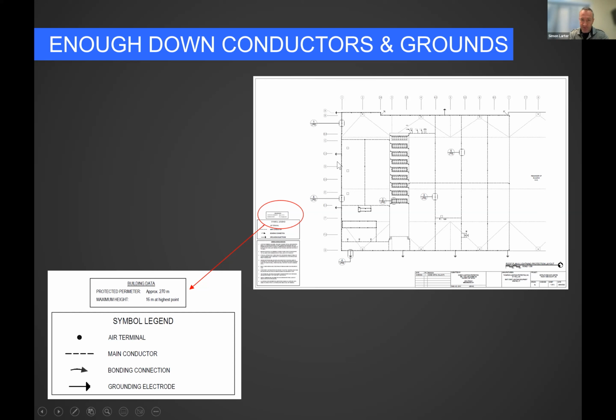Counting around: 1, 2, 3, 4, 5, 6, 7, 8, 9, 10 - I've got more than I need. I always try to put one extra in just in case. 270 meters divided by 30 meters on average means at least 9 down conductors are needed. I've given it 10, so we know I'm compliant with code.